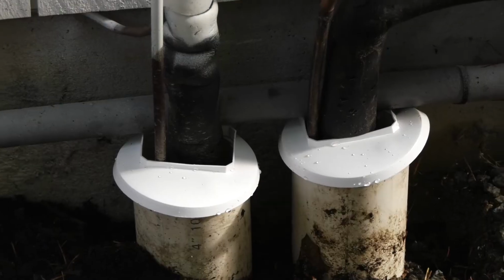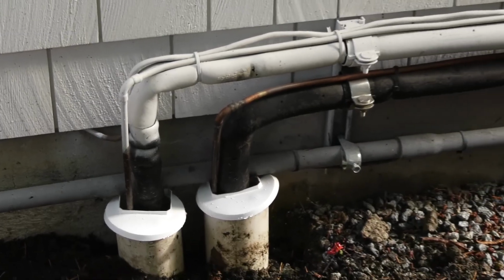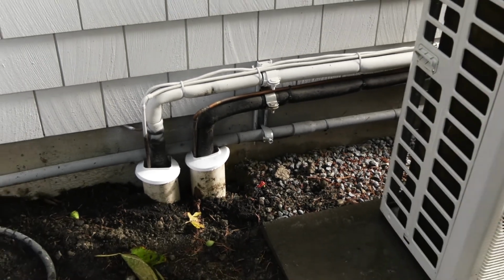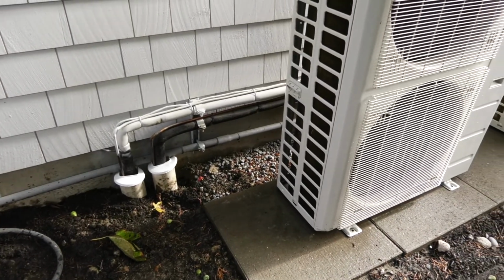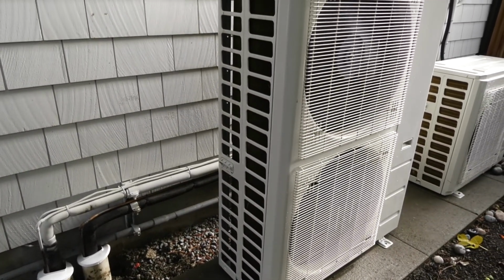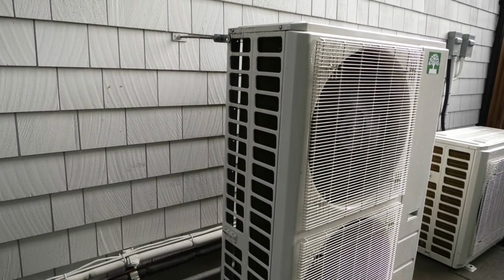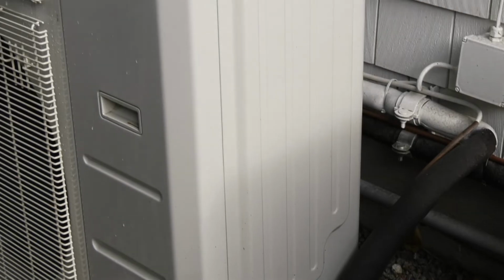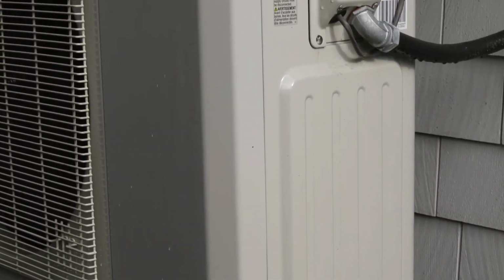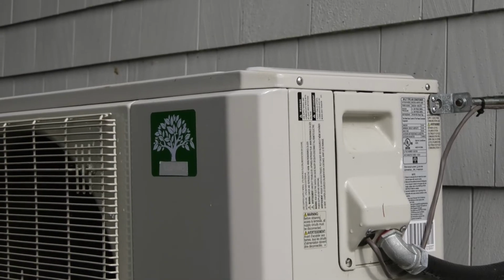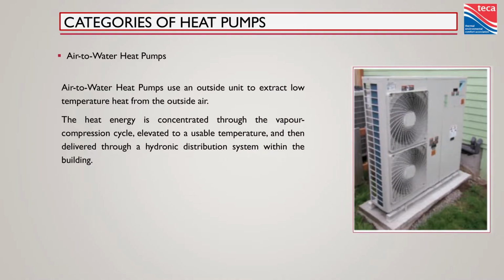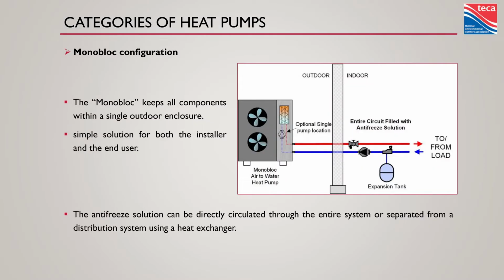But glycol also impacts water flow and pressure drop. So there's some key things to understand about sizing pipes and sizing pumps once you've added glycol. We live in a pretty mild climate here where a lot of people get away with hydronic heating with 100% water. As soon as you run those water lines outside, please, glycol is now your friend. So you might have to educate yourself a little bit on how it works, how to add it, how to verify how much is in there, but key part of any monoblock heat pump. So classic kind of piping diagram, heat pump sits outside the house, water lines come through the building, into the building to where your mechanical room is, and distributed through the building from there.